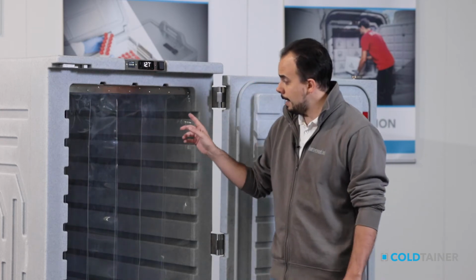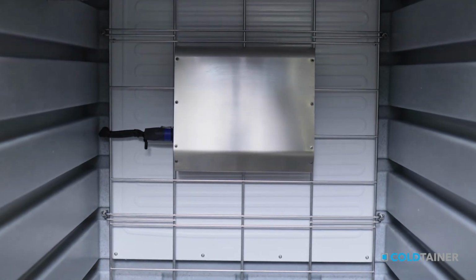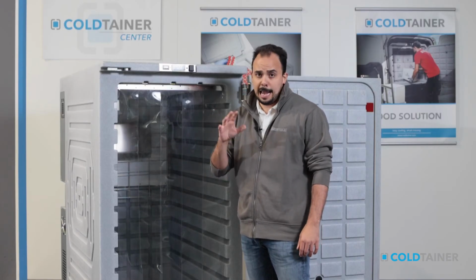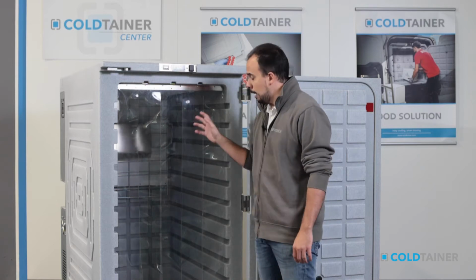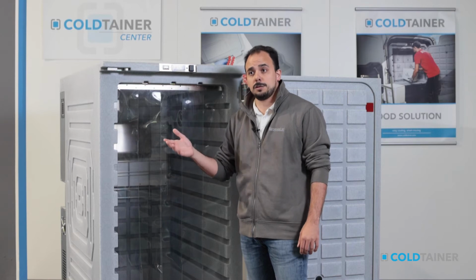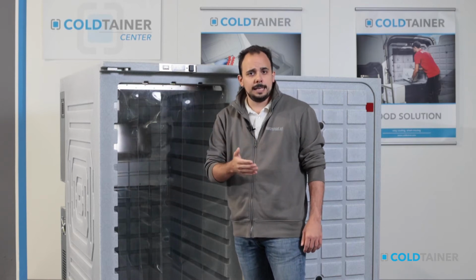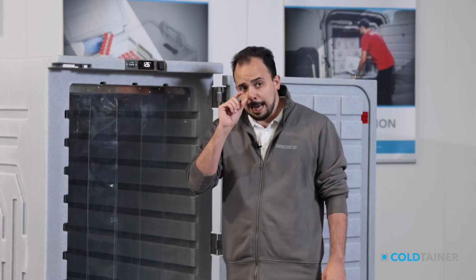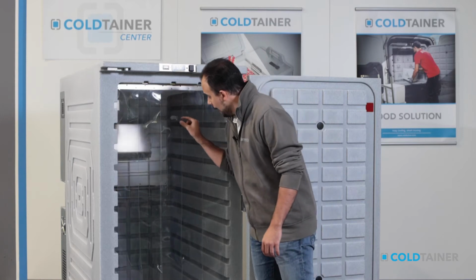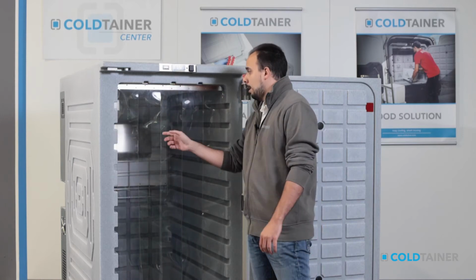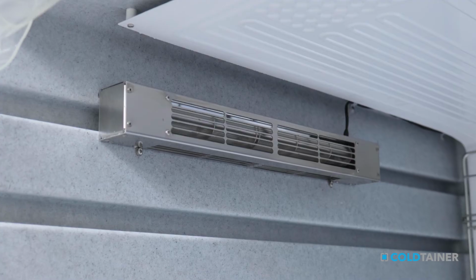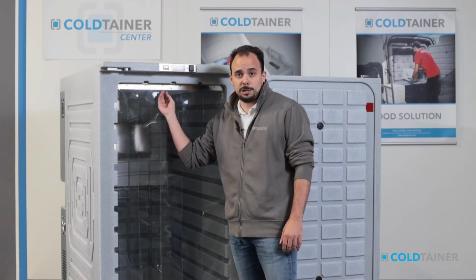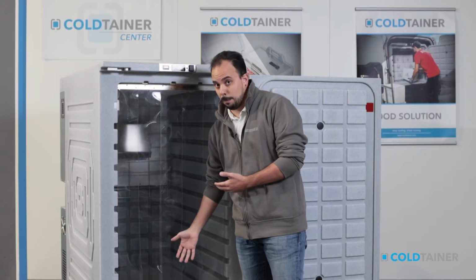Another fundamental feature of this model, the NDH, is the steel box inside. That is a PTC heater, an air-to-air heat exchanger that allows it to maintain a positive temperature of up to plus 30 Celsius degrees, even if it is freezing cold outside. This unit has its own fan on the bottom and an additional fan on the left side of the box. This allows a constant, very smooth airflow inside, so there isn't only hot air on the top of the container and a lower temperature on the bottom.